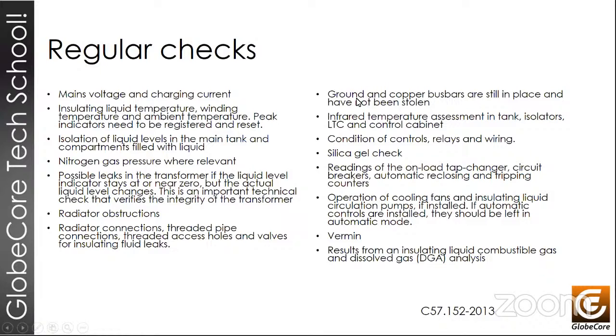Indications are often ignored or left in poor condition, but they could otherwise give us good and valuable information. We need to check operation of cooling fans. It's important in transformers that are equipped with them. And even check for vermin. At one time during transformer maintenance, a dead animal was found between the gratings. And the body of that animal was about 3 months old. So these are the things that we need to check.